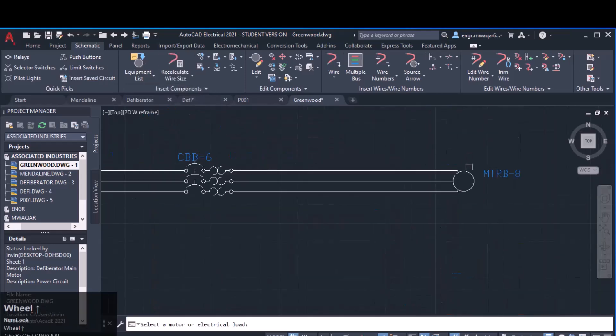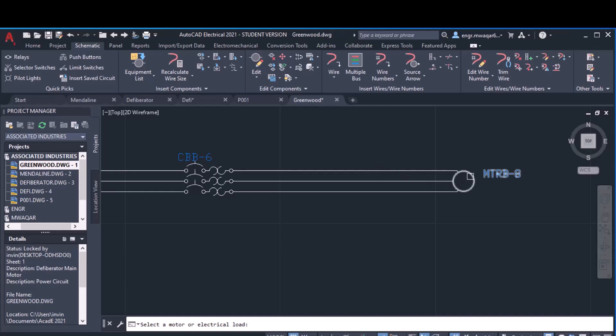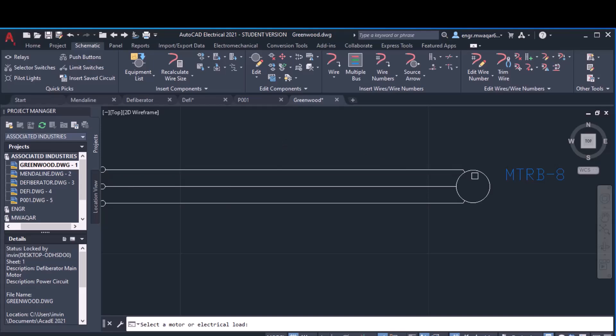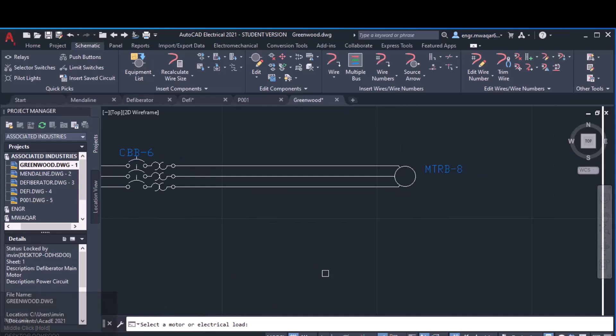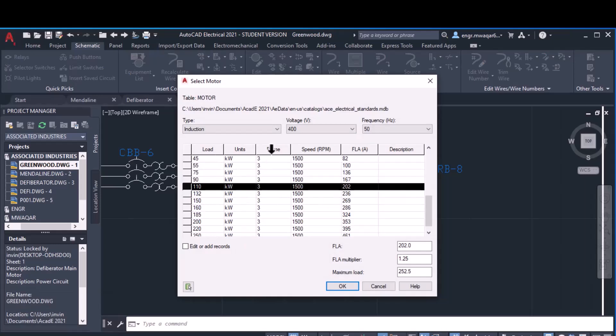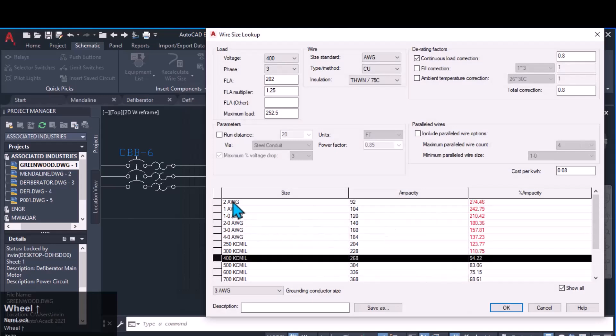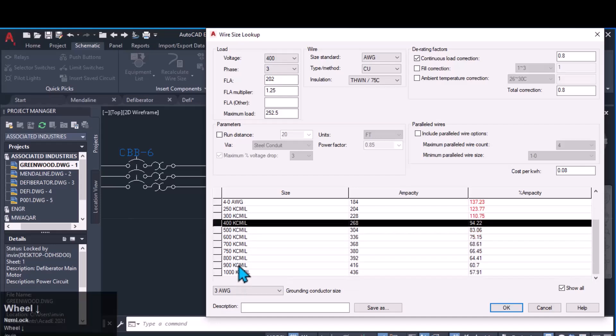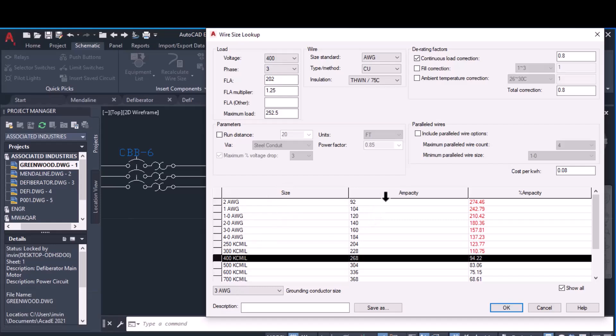Wire recalculate is important — sometimes you need to adjust the wire size according to the load connected. If you have different loads connected with different forms of wires, it will create problems and the drawing will not be accurate. To use it, select a motor or electrical load and enter it. You can see all the attributes come up: load, units, voltage, speed RPM, full load ampere, frequency — everything is mentioned. In this list you can also see different wire gauges with ampacity and percent ampacity mentioned.